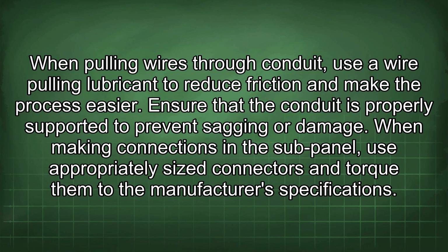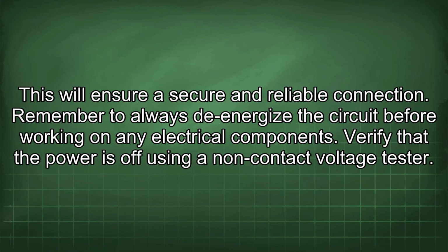When pulling wires through conduit, use a wire pulling lubricant to reduce friction and make the process easier. Ensure that the conduit is properly supported to prevent sagging or damage. When making connections in the sub-panel, use appropriately sized connectors and torque them to the manufacturer's specifications. This will ensure a secure and reliable connection.